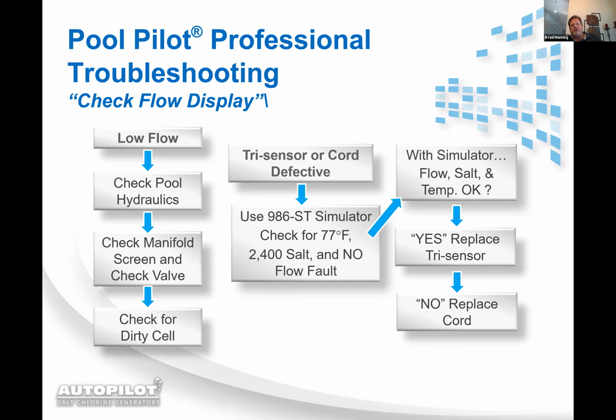You want to check and make sure the union screen's not caked up with stuff. You want to make sure that the cells aren't scaled up, especially when using the PPC5, or what used to be the CC15 cells. There's 15 blades in there, and it's very easy, if there's just slight calcification in between each one of the blades throughout the 3, 4, 5, or 6 cells, whatever you have, that it's not allowing enough water flow to go through the cells.